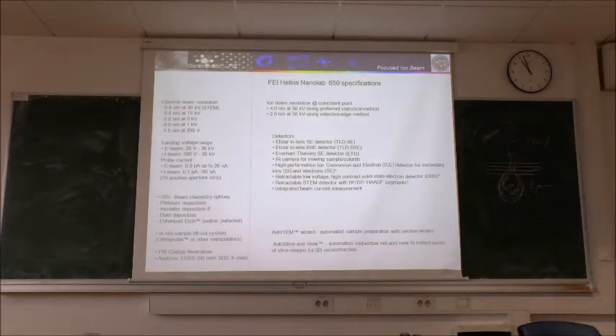These are just briefly the specifications, if somebody is interested, but you can find this on the internet. The electron beam, this is the scanning electron microscope, has really good resolution. Also at 1 kilovolt it's below 1 nanometer, and this is due to the monochromator. This column has a monochromator at the top, just below the electron source, which even improves the resolution at lower energies. It ranges from 20 volts to 30 kilovolts. We are still talking about the electron beam. The landing voltages for the electron beam are 20 to 30, and for the ion beam half to 30 kiloelectron volts.